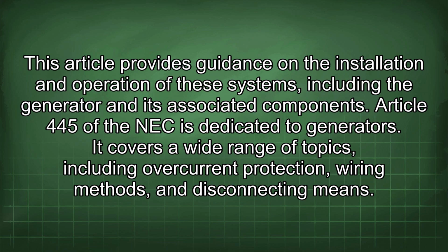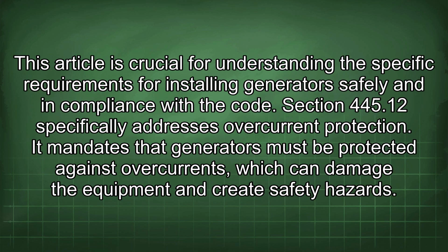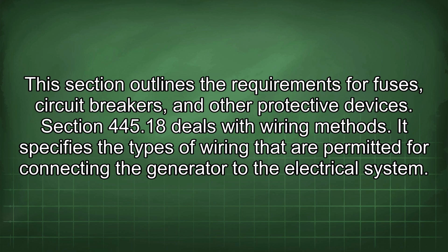Article 445 of the NEC is dedicated to generators. It covers a wide range of topics, including overcurrent protection, wiring methods, and disconnecting means. This article is crucial for understanding the specific requirements for installing generators safely and in compliance with the code. Section 445.12 specifically addresses overcurrent protection. It mandates that generators must be protected against overcurrents, which can damage the equipment and create safety hazards. This section outlines the requirements for fuses, circuit breakers, and other protective devices.